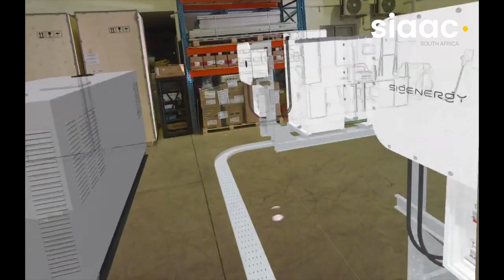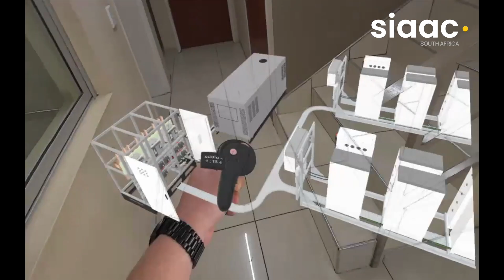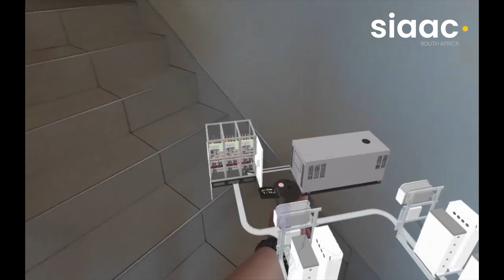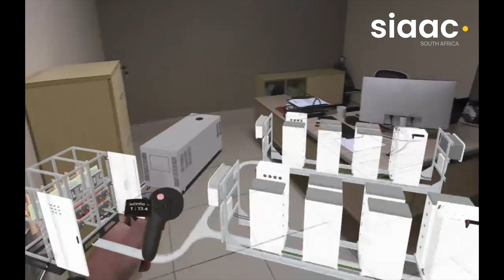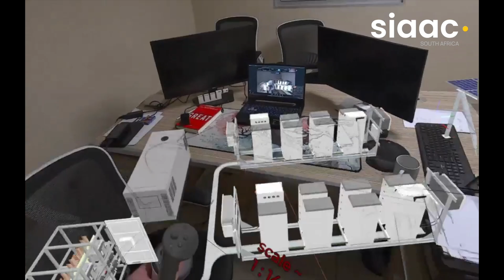Okay, so the program gives us the flexibility to change the design. What happens? So fair enough, the program was supposed to be locked, or the design was supposed to be locked, and we messed around with it by moving the genset. But if it's not locked and we move the genset, what happens to the cabling and the sizing of the cabling? Because I noticed that the cable tray stayed where it is, even though the genset moved. Is that something the program will take care of automatically? Yes, that's correct. So in a later phase, we're busy ironing out the cabling system, but it's good that you asked.